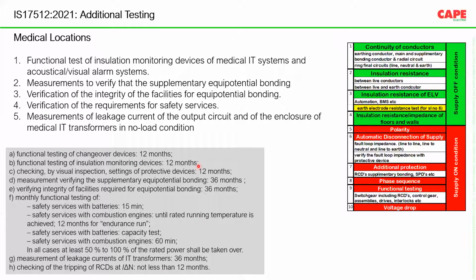Measurement to verify that the supplementary equipotential bonding is correct. Of course, every 36 months you are supposed to do. Integrity of required equipotential bonding, main equipotential bonding, every 36 months. Like that, the standard very clearly defines what kind of safety measures are required, what kind of extra safety measures are required in the medical location, and what kind of extra testings are required in the medical location. All these things are very well defined in this particular standard.